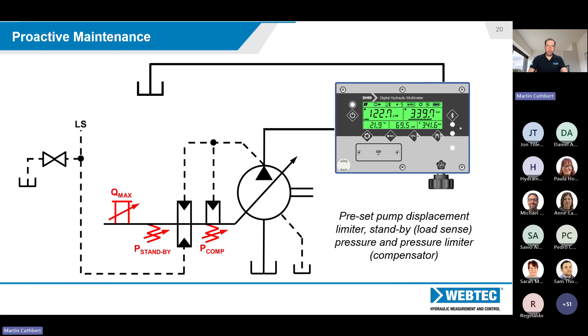There's also the case where when pumps get replaced, the new pumps aren't preset in the factory. They have to be set in the field. And so once they're installed, you can then use the tester to set up max displacement, standby pressure, compensator pressure. And so those examples you can see there with the graphs, you could do that numerically. So you could just see, right, that Q max, what am I achieving on the screen? So you could just look at that number and go, yes, I've achieved that.